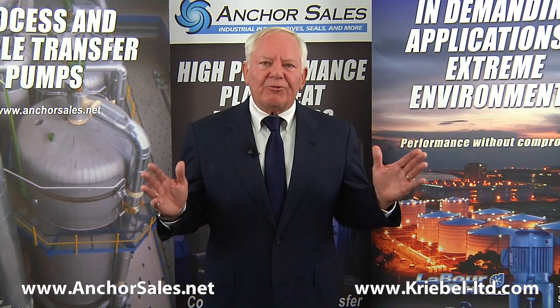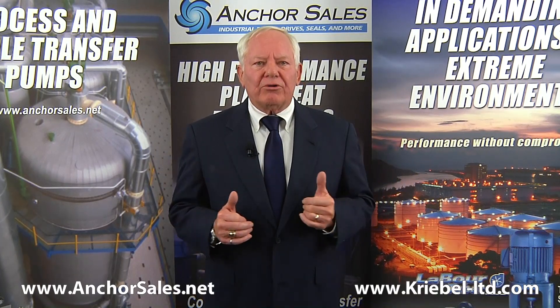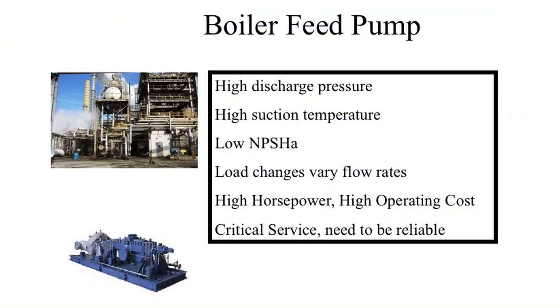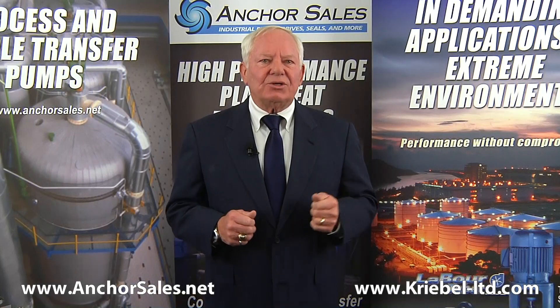Despite the wide range of pressures, all boiler feed water pumps have certain parameters in common: high pressure discharge, high suction temperature, low NPSH available, the need to operate over a wide range of flows, high horsepower and the need to be efficient, and because they are integral to the operation of the boiler, they must be extremely reliable. Let's look at each parameter.